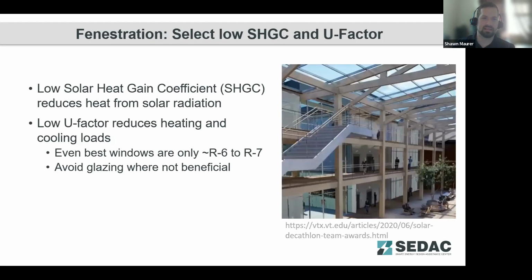For fenestration, again, select low solar heat gain coefficient glass and low U factor glass. It's going to reduce how much heat is coming into the building and how much heat is lost out of the building. So one thing to consider though, if you're looking at a building, even the best windows that we have on the market are about an R6 to an R7 overall insulation quality, compared to most of our wall designs, which are somewhere between an R20 and R18 kind of average for the insulation value. So even the best windows have a significantly less insulation value than an opaque wall assembly. So proper design to minimize how much glazing your buildings have, while preserving views to the outdoors and daylighting coming into the building, will go a long way towards high performance design.